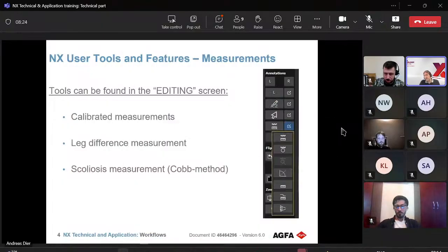And then we just have to look: the bone that I want to measure is maybe, when the patient lies there, again 10 centimeters above the table. So on the whole, we have 18 centimeters. And this is the value that we have to enter in this function to get the calibration done. But as said, this only works if the system knows the SID.